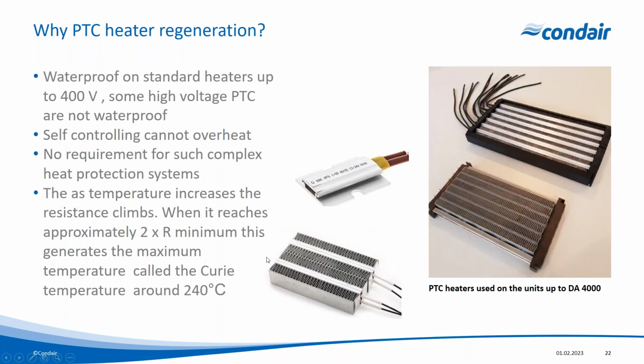Now, we mentioned regeneration heat. This is one of the critical aspects. There's two critical aspects of it. Obviously, the rotor and the technology within the rotor and the desiccant wheel is absolutely critical. But also the method of heat is critical as well. We use PTC heaters for the regeneration heat. And on a freezer application, it's incredibly important that they're waterproof.